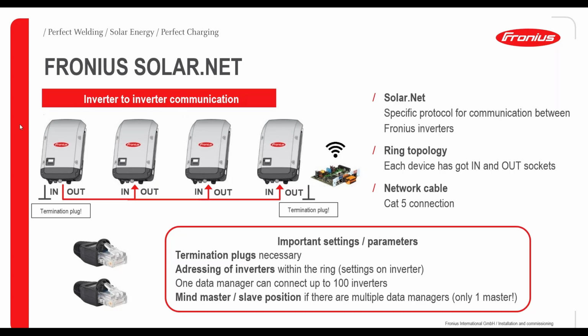For example, with a system of 4 inverters, we connect every inverter to another, making sure it forms a ring topology - we have to close the ring. That's why we have termination plugs on the first and last device. Once the ring is closed, all the data is collected by one data manager. This data manager card is inserted into one of the devices and stores all the data produced by the 4 inverters - essentially all the production data of the whole system. It can then be connected to the internet and send the data to SOLAR.WEB and so on.